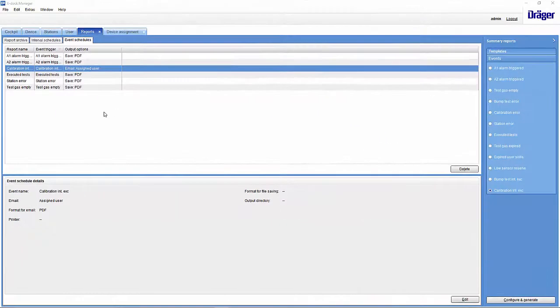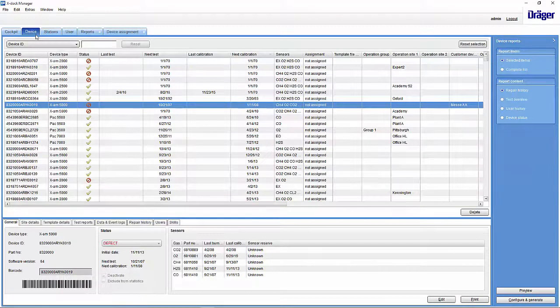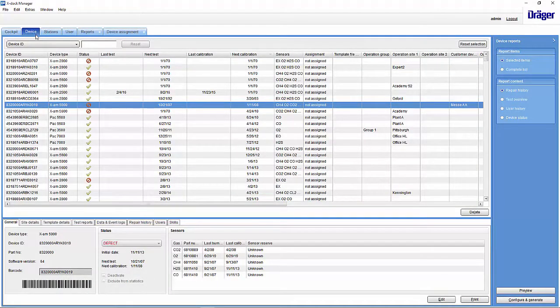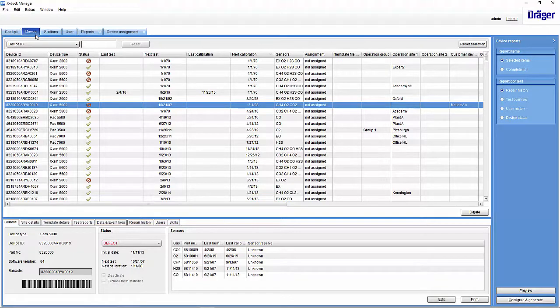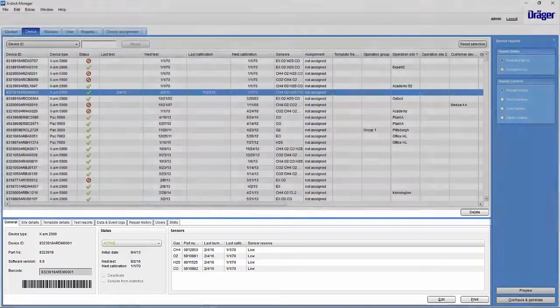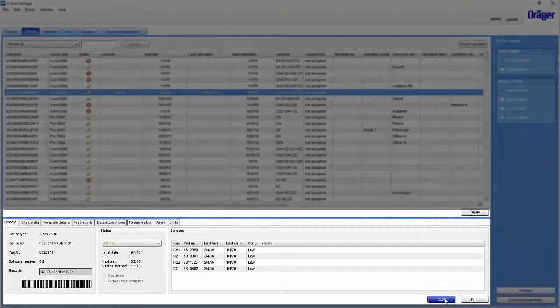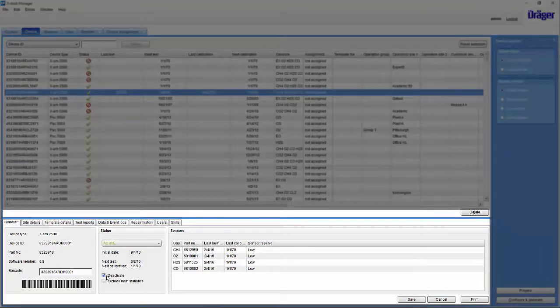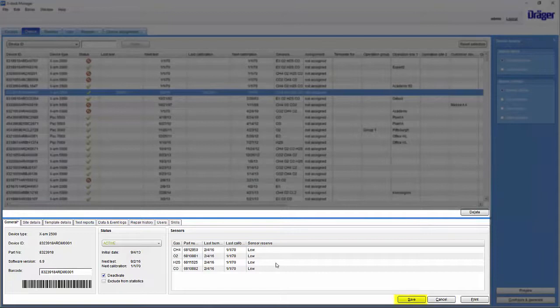One final tip. If you have not selected the option to issue an error when the interval has expired, you can still lock the instrument using the X-dock Manager. To do so, select the desired instrument on the Device tab, click Edit, select the Deactivate checkbox, and save the changes. The instrument will be locked the next time it is placed into the X-dock.